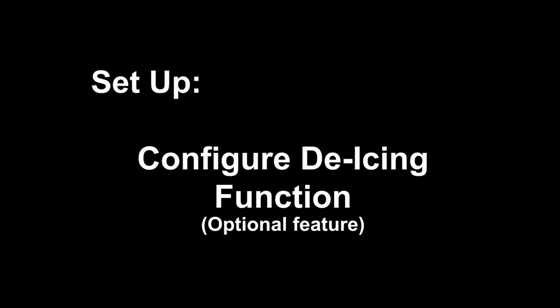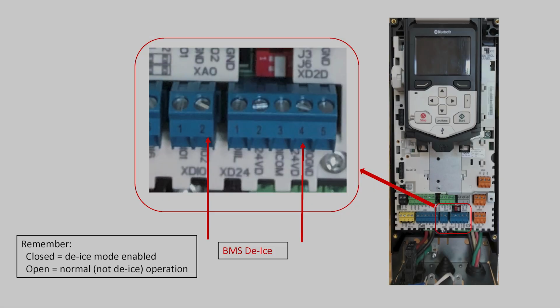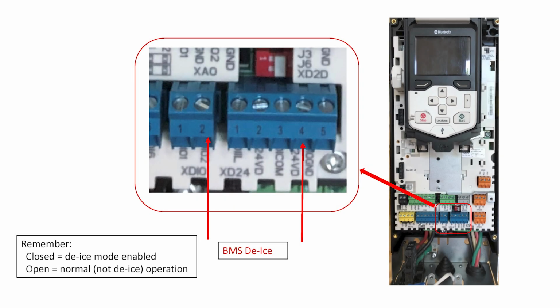Now, let's configure the optional de-icing operation. De-ice runs the motor in reverse at a slow speed to prevent ice buildup. For information on operating the equipment in cold weather, see the BAC Product Operation and Maintenance Manual. The optional BMS de-icing command has leads to terminal XD24-4 and XDIO-2. De-ice is triggered by a closed contact call from the BMS on digital input 2, wired at XDIO-2. If no wires are landed on DIO-2, de-icing will not occur.